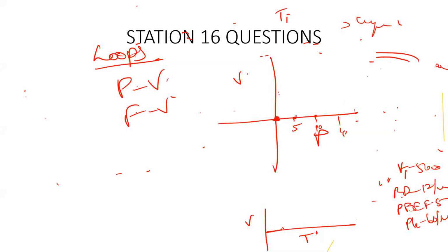When the patient is inspiring with positive pressure, to overcome the airway resistance and the alveolar resistance offered, the loop will be like this in inspiration. Once the maximum inspiratory point is reached, which is the tidal volume of 500 ml, the expiration drops like this. So this is a normal pressure volume loop in volume control ventilation.